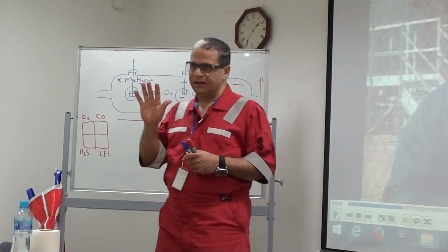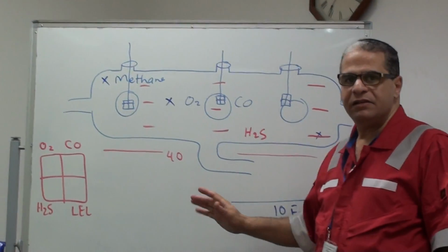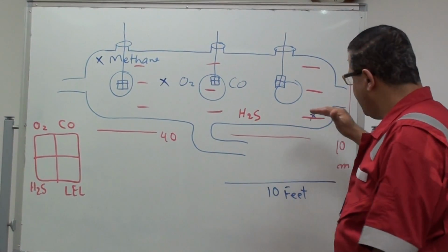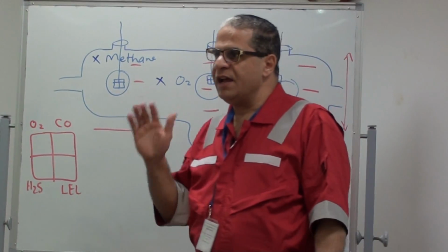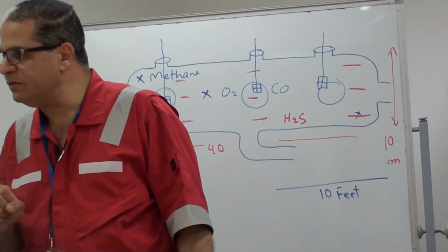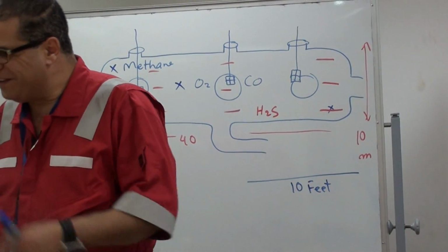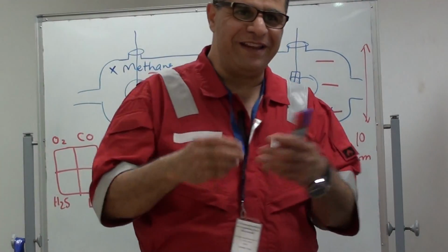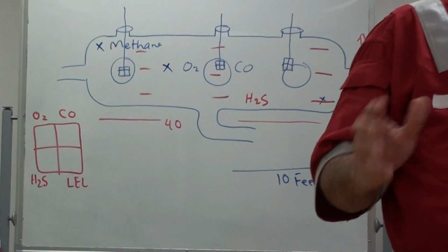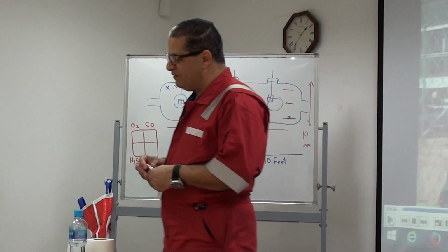So the technique should emphasize the following. Each 10 feet, you take one occasion at 3 different levels. Each level should be considered as one separate occasion, after which you have to take the apparatus out, reset the apparatus, flush the tube with air, or give a chance for the tube to clean itself by the action of the pump, provided that you are situated in a fresh air environment.